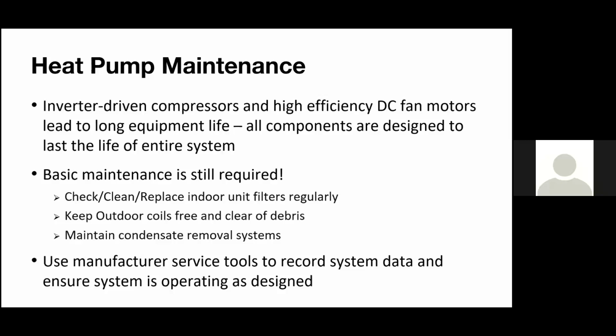And then lastly, what's pretty important is maintain condensate removal for these systems. So if we're looking at an indoor unit, kind of go up there when you're maybe replacing the filters, check the condensate, see if the pan is blocked off, see if the pipes are blocked off, anything like that. See if the pump is operating and running. That way you don't get any clogs, anything like that. If the pump fails and maybe you ruin some ceiling tiles or furniture down below, you want to stay away from that. If you can do gravity drain, gravity always wins. I know a lot of the time that doesn't really work, because typically you're going to need some kind of lift through your plenum. But just something to think about there.